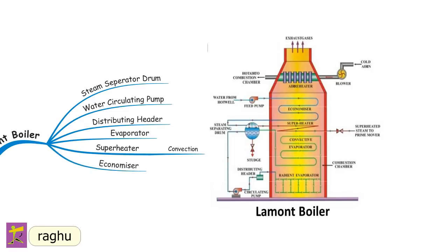The economizer preheats the feed water using exhaust gases flowing out from the boiler to the atmosphere. The preheated water requires only a small amount of additional heat in the boiler, which increases boiler efficiency. The feed water supplied by the feed pump is heated in the economizer on its way to the steam separator drum. The air preheater uses exhaust gases to preheat air, which is then supplied to the furnace for combustion.